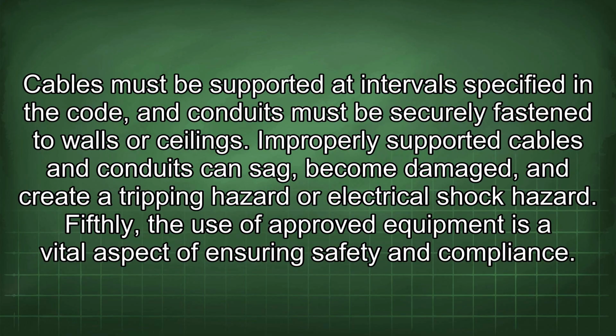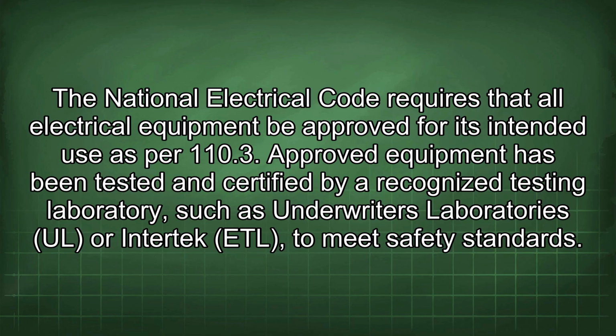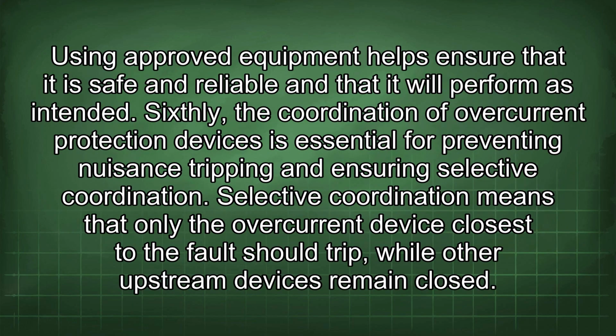Fifthly, the use of approved equipment is a vital aspect of ensuring safety and compliance. The National Electrical Code requires that all electrical equipment be approved for its intended use, as per 110.3. Approved equipment has been tested and certified by a recognized testing laboratory such as Underwriters Laboratories (UL) or Intertek (ETL) to meet safety standards. Using approved equipment helps ensure that it is safe and reliable and that it will perform as intended.